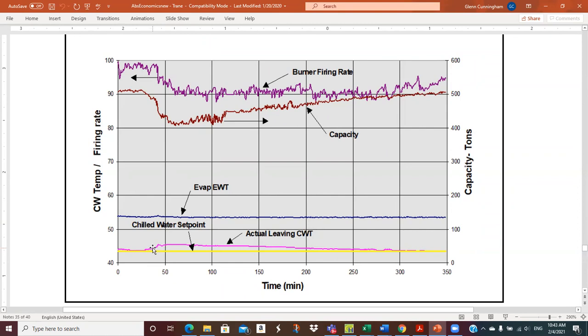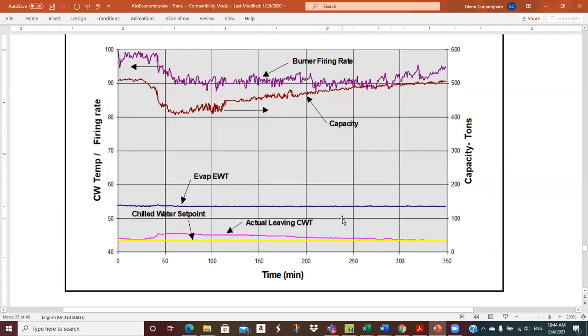Now we do get a bump in leaving chill water temperature. If that's 44, maybe 46, something like that, 45 and a half, 46. So maybe 1.5 degrees, 2 degrees on chill water, which is not huge. And you don't see much of a change in the returning water temperature. So that would say it probably didn't really affect anything too much. But you see over the course of a couple of hours, then the purge cycle works and the capacity comes back up and the burner firing rate stayed stable through that whole period. So we didn't crystallize, and then gradually we start increasing once we get the machine back in proper operating condition. The firing rate goes up, capacity goes up, and we pull the leaving chill water temperature right down to the set point. Pretty interesting.